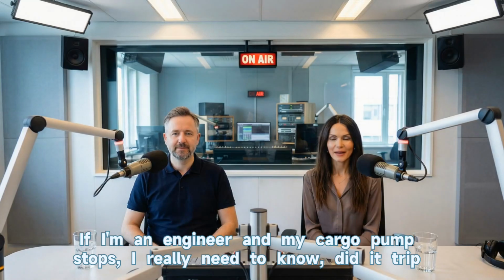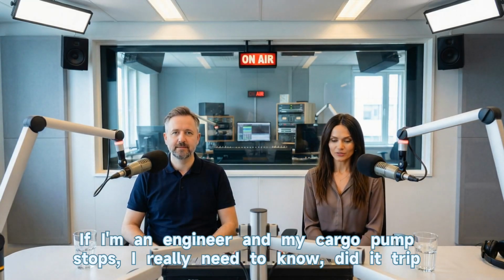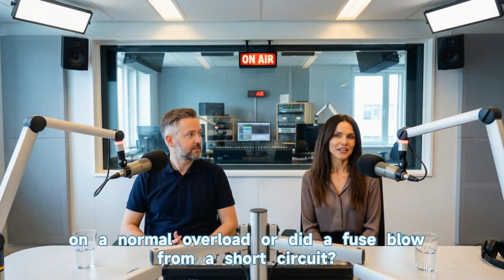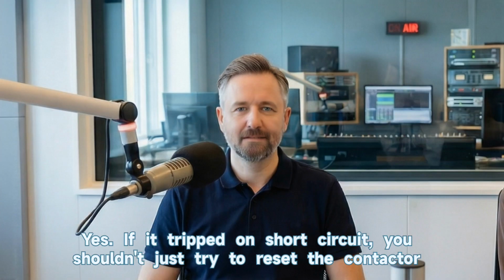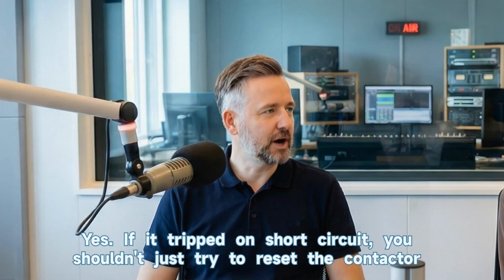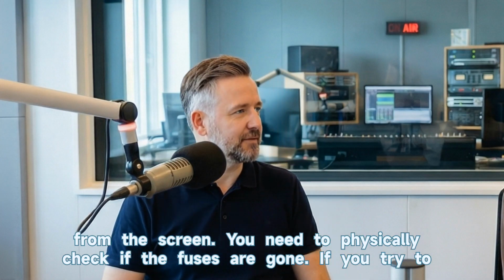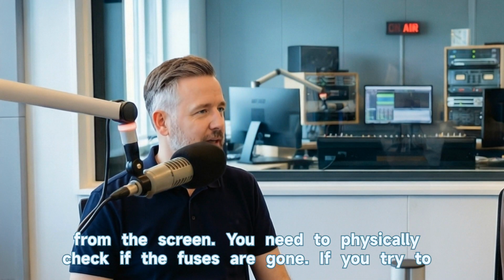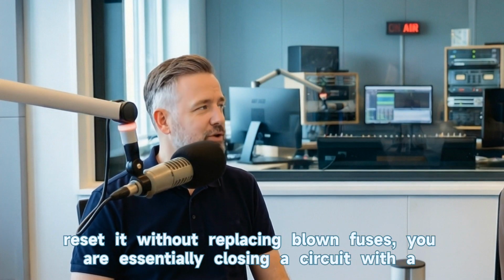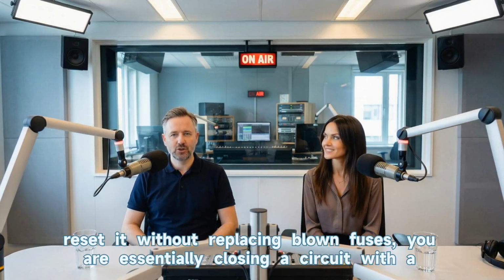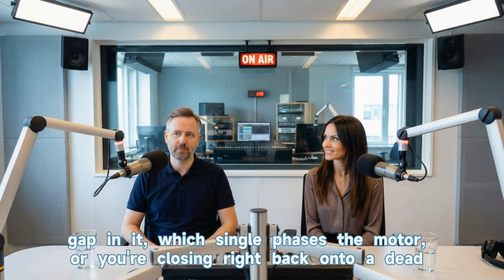If I'm an engineer and my cargo pump stops, I really need to know, did it trip on a normal overload or did a fuse blow from a short circuit? Yes. If it tripped on short circuit, you shouldn't just try to reset the contactor from the screen. You need to physically check if the fuses are gone. If you try to reset it without replacing blown fuses, you are essentially closing a circuit with a gap in it, which single phases the motor, or you're closing right back onto a dead fault.